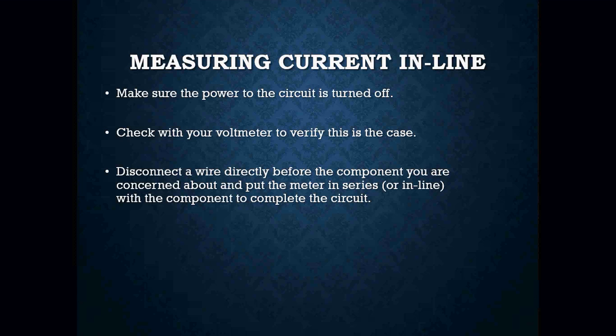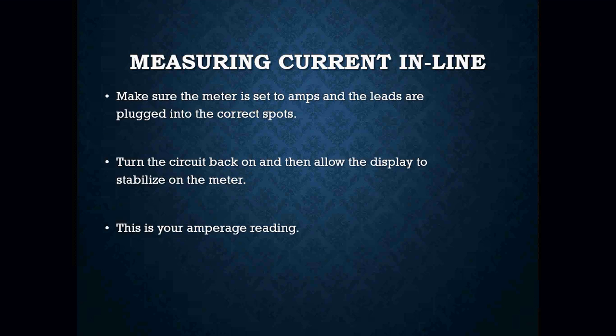Okay, so again, when you're taking an inline current reading, you have to make sure that the power to the circuit is off. You're going to check with your voltmeter to verify this is the case. Always, never assume that the power is off. You want to definitely double check that it is indeed off. You are going to disconnect the wire directly before the component you are concerned about and put the meter in series, or in line, with the component to complete the circuit. Make sure that the meter is set to amps and the leads are plugged into the correct spots. You're going to turn the circuit back on and then allow the display to stabilize on the meter, and again, that's going to be an amperage reading.